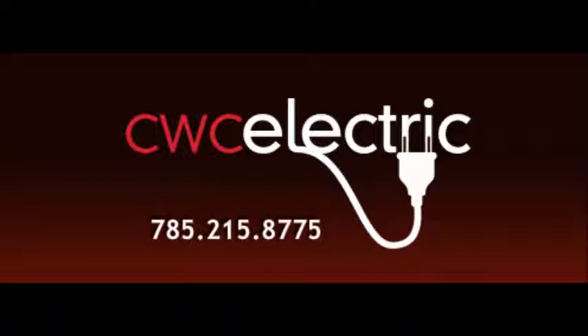If you're tying a generator into your electrical system, you have to have installed a proper transfer switch so there's no way utility power and generator power can both be on at the same time inside the electrical panel. If utility power was turned on and that line voltage hit your generator, it could cause severe damage, injuries, or death. On the reverse side, if electricity from your generator goes out onto the power lines through the transformer, you can actually electrocute the lineman trying to repair the lines feeding your house. So if you're tying into your electrical system, you have to have a proper transfer switch.